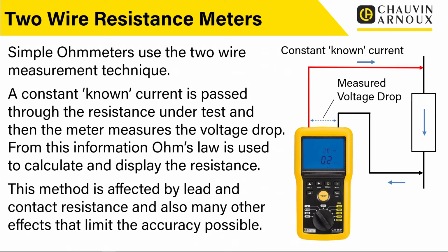So if you look at the diagram on the right hand side there, you can see what's going on. We've got our insulation continuity tester there, the 6524, and we're carrying out a 2-wire measurement. So both leads are used for effectively voltage and current. We pass a known current through the load, through the resistance, and we measure the volts drop across the 2 terminals. And because we've got current and we've got voltage, we can work out what the resistance is using Ohm's law, and that gives us our measured value.